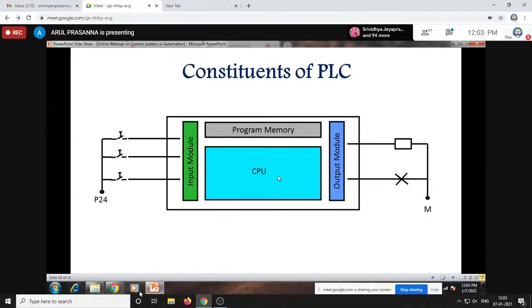The input module and output module act as an isolator between the high voltage inputs and outputs and the low voltage CPU. Universally all CPU ICs or controller ICs work with 5 volts. If you give a 5 volt input through your input terminals, you can directly connect with the CPU. But in a PLC, we have a processing voltage of 12 to 24 volts. Since that cannot be directly connected to the CPU pins, it is passed through an input module, and similarly an output module.